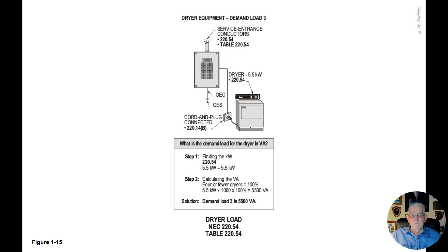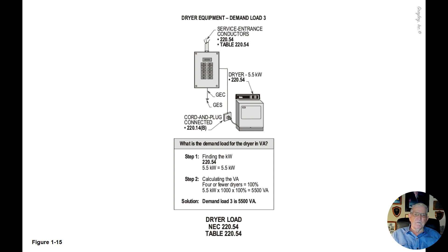Multiplying 5.5 kW by 1000 converts it to a VA rating: 5500 VA. The demand load for this single dryer is 5500 VA. To summarize, Figure 1-15 illustrates figuring the VA for four or fewer dryers calculated at 100%.